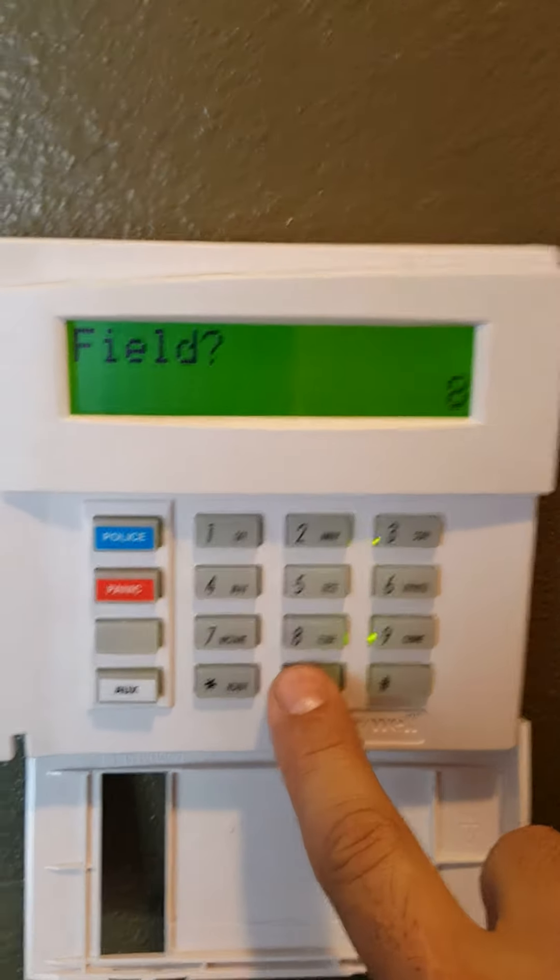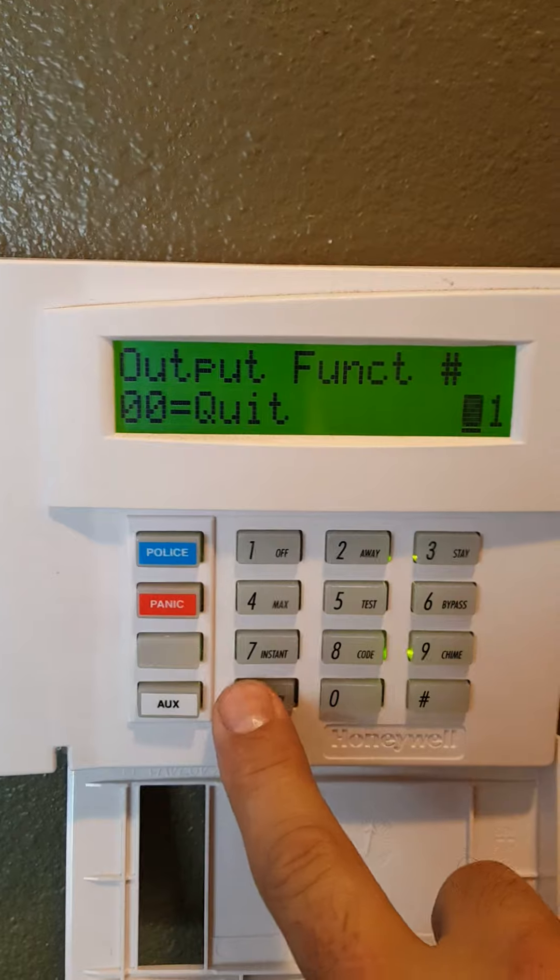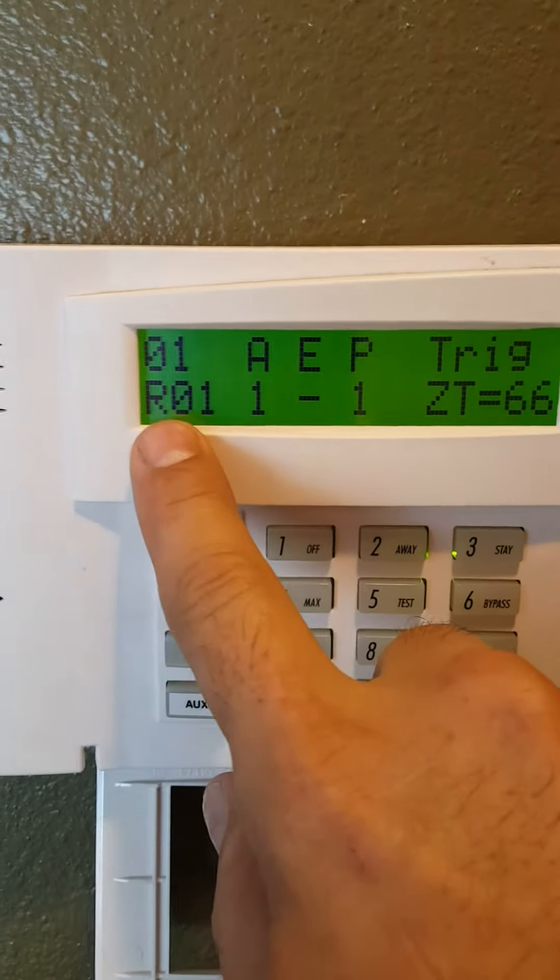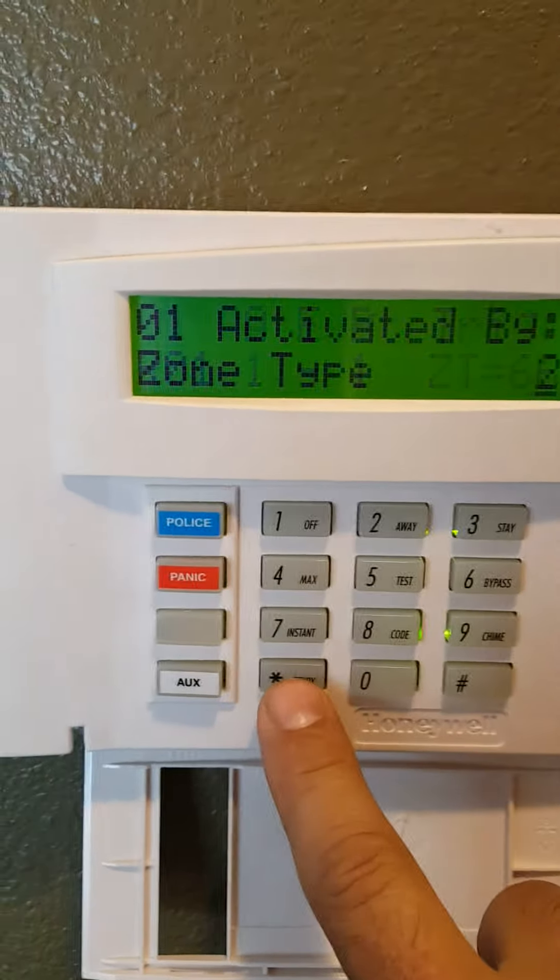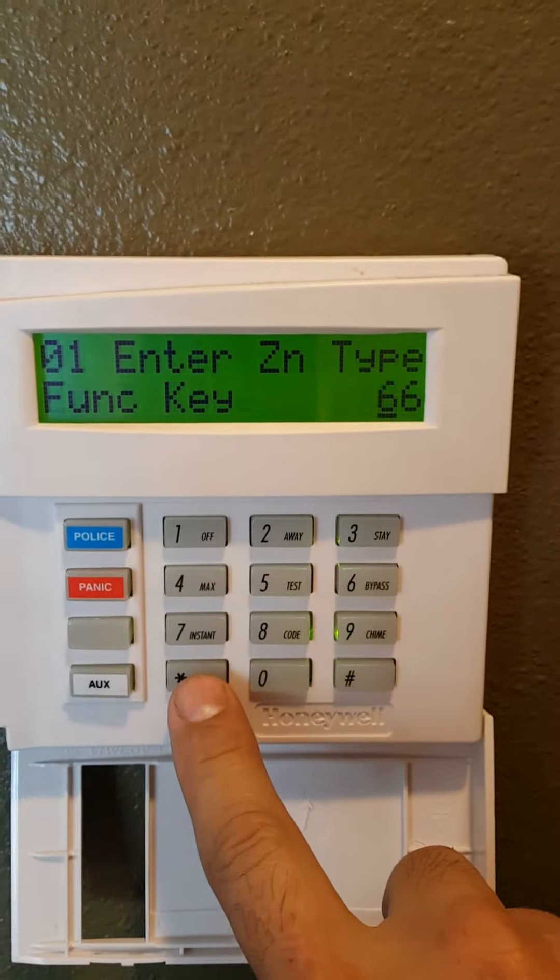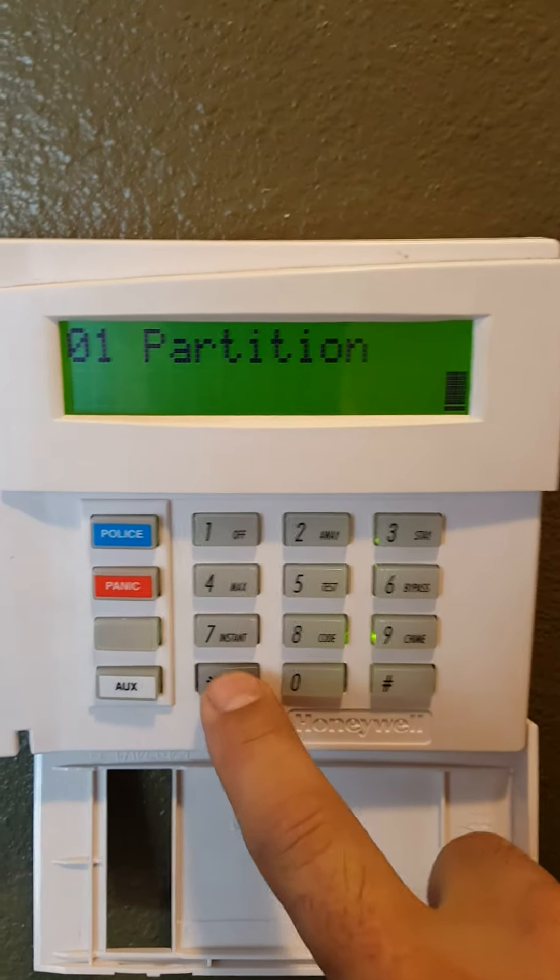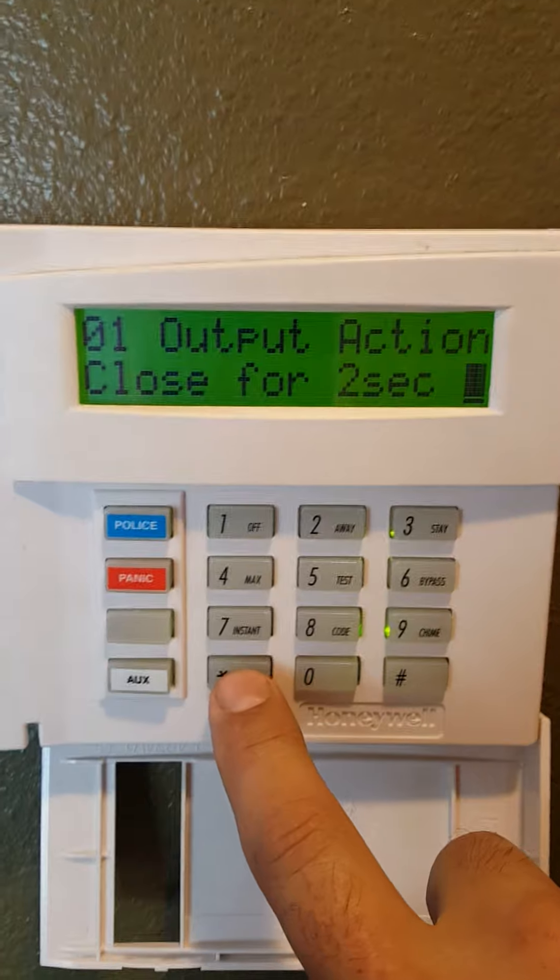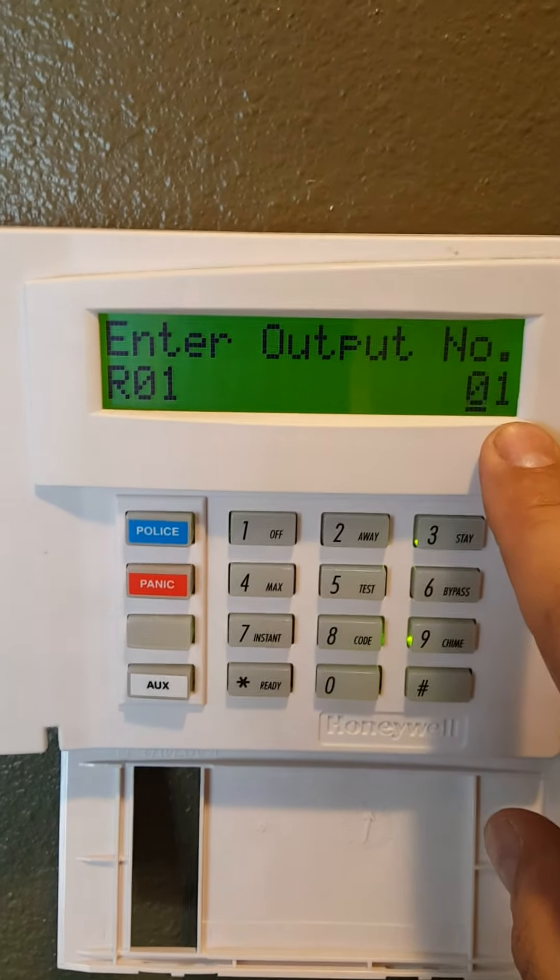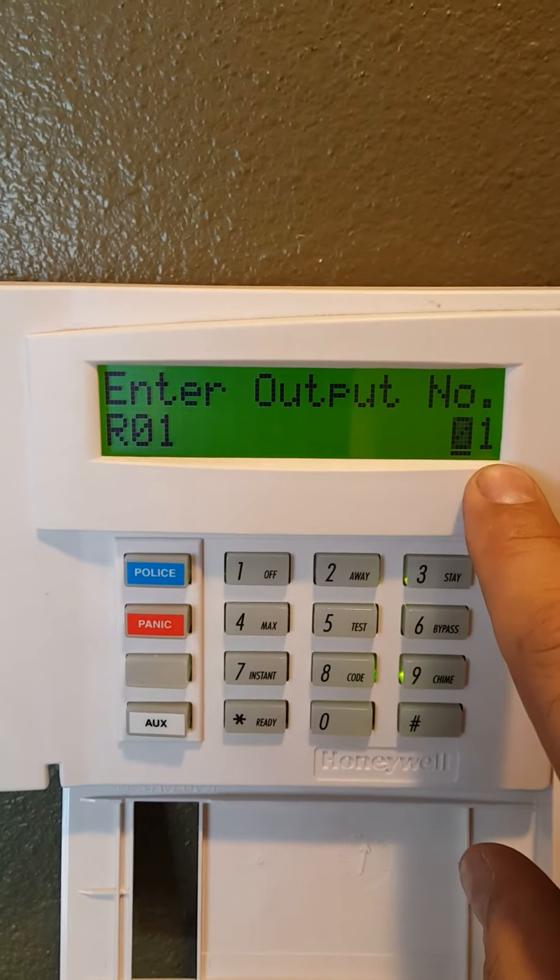Let's go into star. It says 17, so now we're on relay 1. The changes are: zone type 2, function key 66, partition 1, and we want that to close for 2 seconds. Where it was 17, the first relay on the expansion board will be 1.